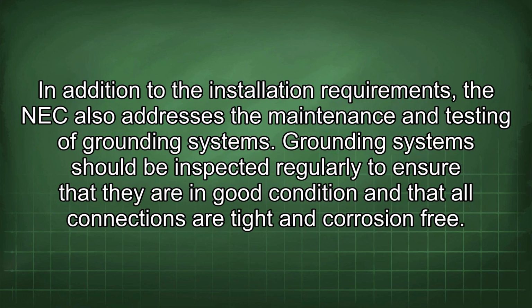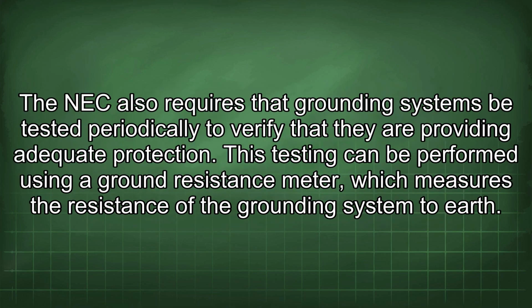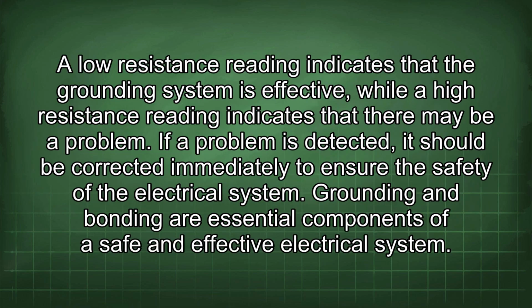In addition to the installation requirements, the NEC also addresses the maintenance and testing of grounding systems. Grounding systems should be inspected regularly to ensure that they are in good condition and that all connections are tight and corrosion-free. The NEC also requires that grounding systems be tested periodically to verify that they are providing adequate protection. This testing can be performed using a ground resistance meter, which measures the resistance of the grounding system to earth. A low resistance reading indicates that the grounding system is effective, while a high resistance reading indicates that there may be a problem.